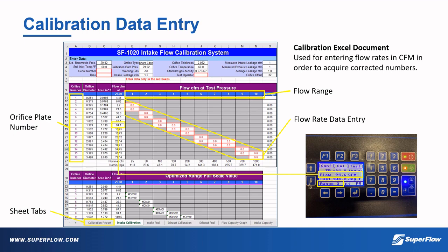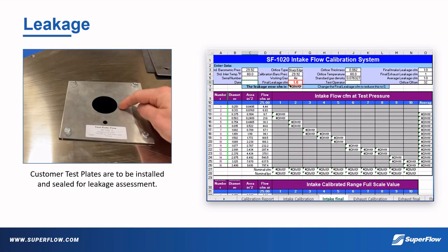Coming back to recording the leakage of the bench, notice there is a box for recording it at the top of the Intake Calibration tab, and similarly on the Exhaust Calibration tab. It should be noted that recording leakage here should be ignored, as the correcting numbers use a similar box on either the Intake Final or Exhaust Final tab, depending on the type of calibration being performed. To find the leakage of a flow bench, the customer's test plate provided with the bench can be used. Normally, a rubber plug would seal the larger hole, while you can use your finger to seal the smaller hole.